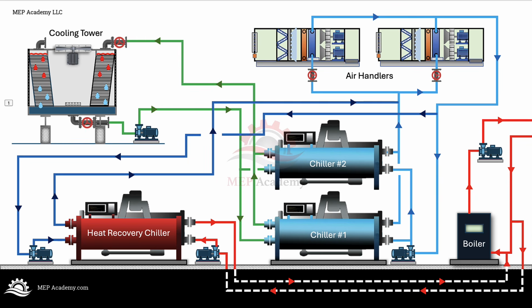That means the heat recovery chiller runs mainly to satisfy a hot water demand. The chilled water becomes the useful byproduct. This can happen in a campus system where the chilled water can be used somewhere else, even if the local building does not need all of the cooling. Some systems can operate in either mode depending on the time of year, the utility rates, the heating demand, the cooling demand, and the plant sequence.